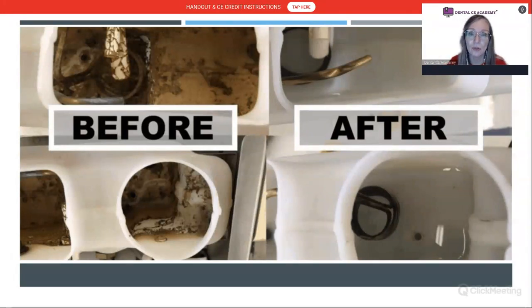What do you need to do in terms of maintenance? Assign it to someone who's in charge. They'll perform the daily, weekly, and monthly maintenance per manufacturer's instructions, and send these out at least yearly for a tune-up. Whatever company you use can leave you a loaner. They'll check the gaskets, calibrate the temperature and pressure, and clean it. It extends the life of these devices, which are expensive. Autoclaves are expensive, but they have to be running correctly, so this is a great investment, but you have to assign it.